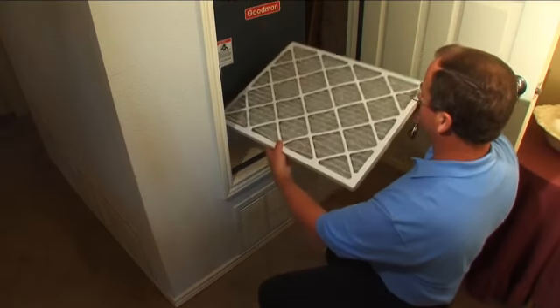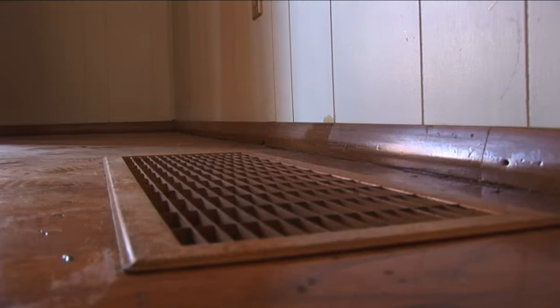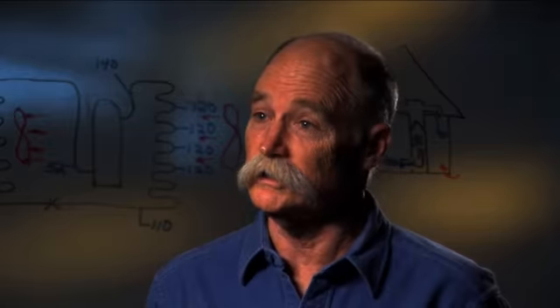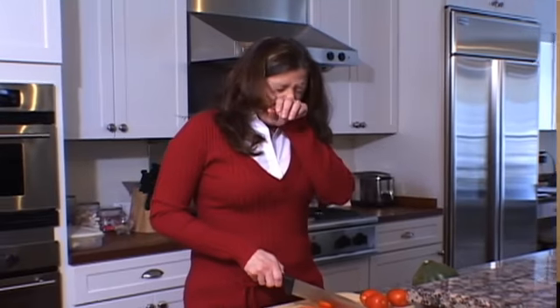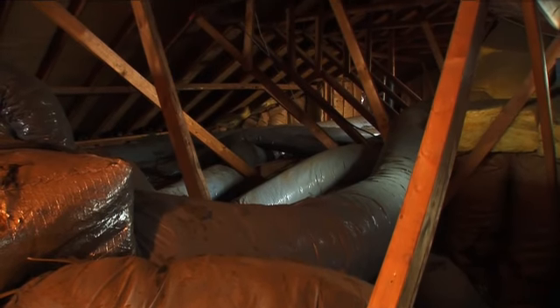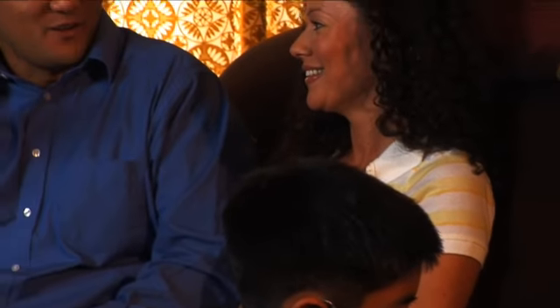Your heating, cooling, and air filtration equipment will also be inspected and tested. A lot of customers see dirt around the registers and think that all they have to do is clean out the ducts. In fact, there's a very high likelihood that what you have is a leaky duct system that's pulled all that dirt into the system. Duct cleaning is not a bad thing to do, and in some cases it should happen, but it is probably not needed as often as many homeowners think. More often than not, the dust that homeowners experience is coming in from all the holes in the house, passing through attic crawl spaces and getting into the distribution system. It is more important to keep that dirt from entering the ducts in the first place. When they're sealed, sized right, insulated, and you have a high-efficiency furnace filter, you'll find that will solve most of your indoor air problems.